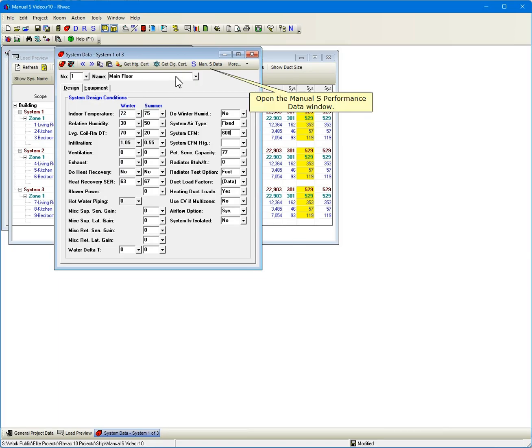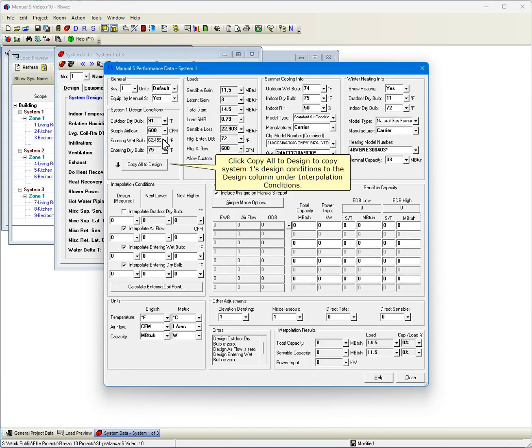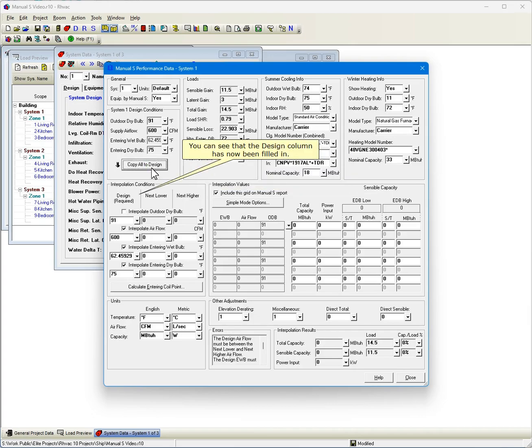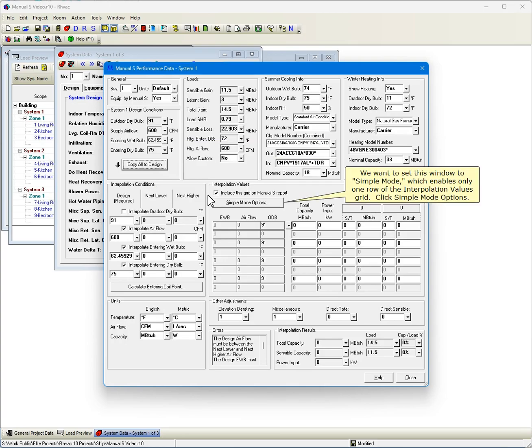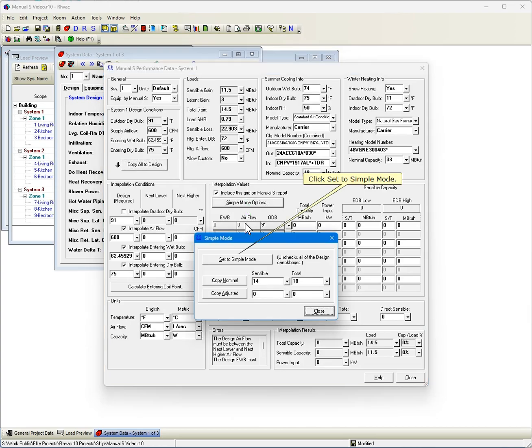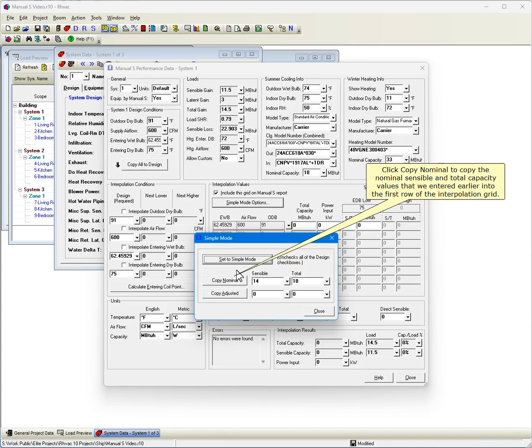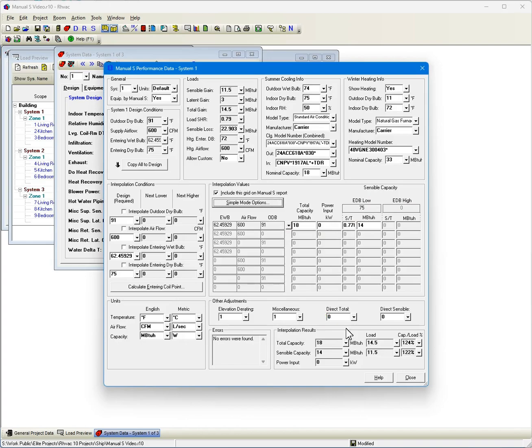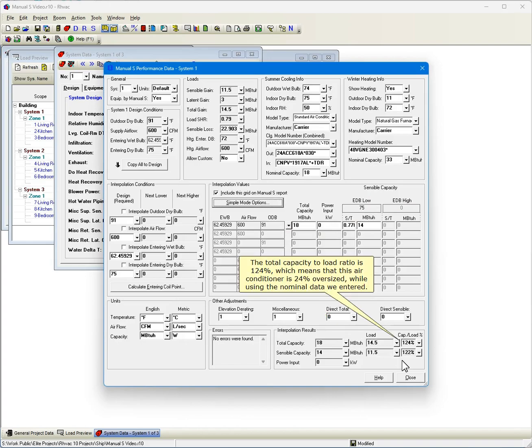Open the Manual S Performance Data window. Click Copy All to Design to copy System 1's design conditions to the Design column under Interpolation Conditions. You can see that the Design column has now been filled in. We want to set this window to Simple Mode, which enables only one row of the Interpolation Values grid. Click Simple Mode Options. Click Set to Simple Mode. Click Copy Nominal to copy the nominal, sensible, and total capacity values that we entered earlier into the first row of the Interpolation Grid. The total capacity to load ratio is 124%, which means that this air conditioner is 24% oversized while using the nominal data we entered.